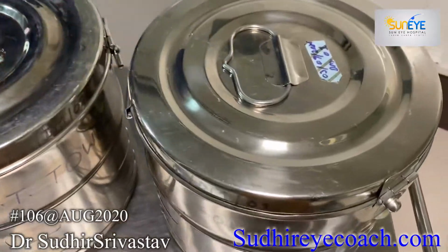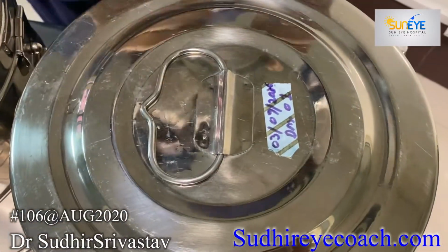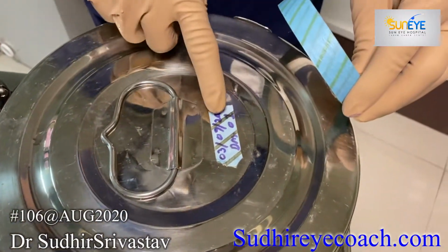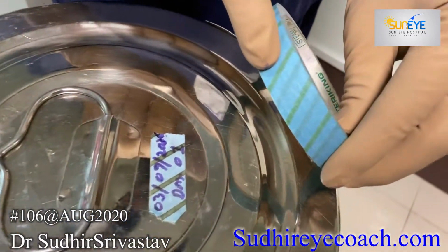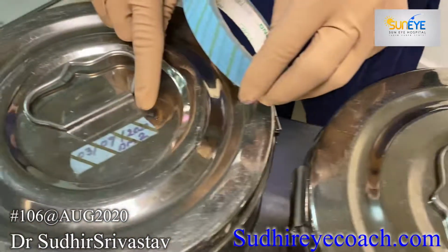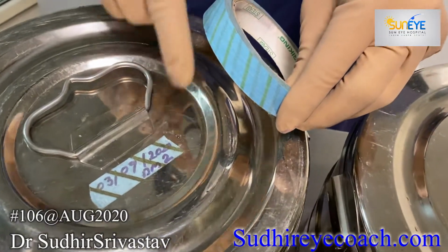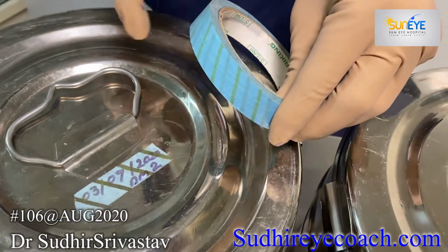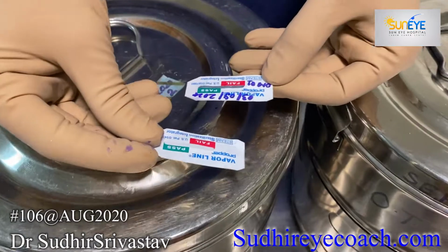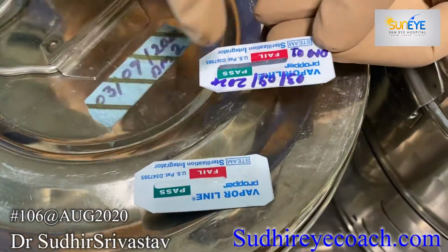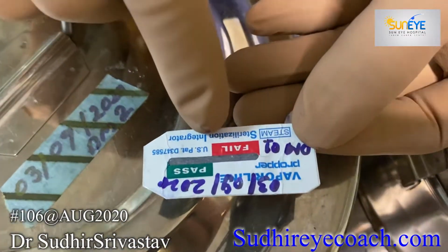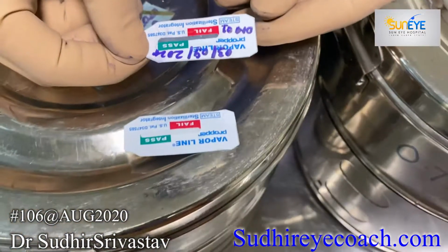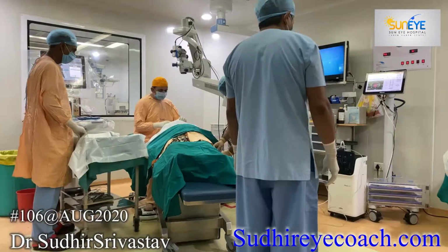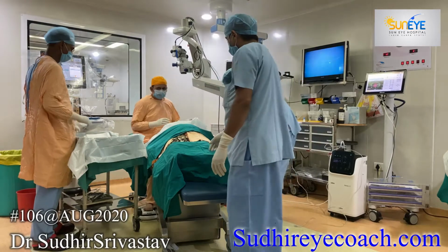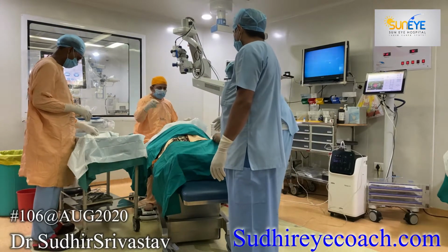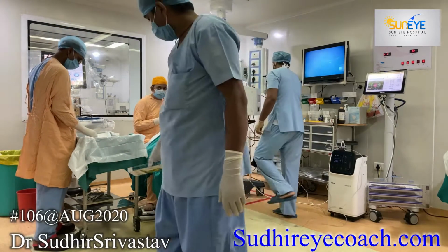Now analyze the color change of the type 1 steam chemical indicator placed on the top of the surgical drum. Yellow strips must turn evenly black, which indicates that proper temperature has been maintained for sufficient time. Type 5 indicators placed inside the drum must be inspected after opening. Even color change indicates the proper exposure of linen to steam for sufficient time. Now sterilized gowns, trolley drapes and other linens are ready for use.